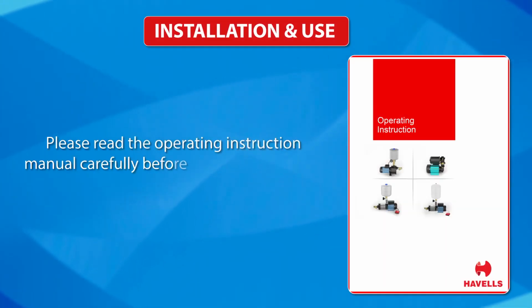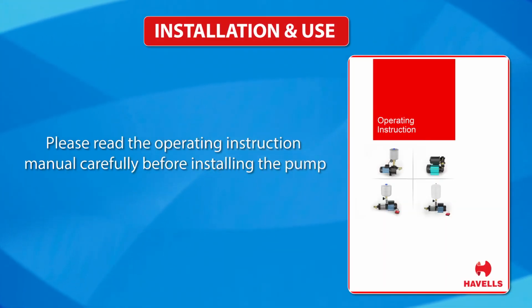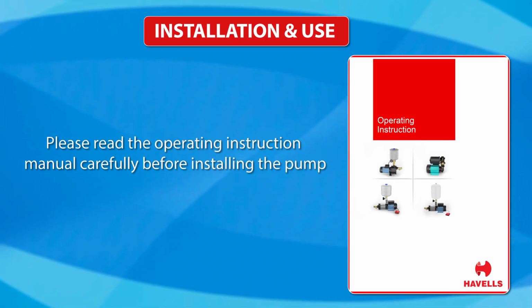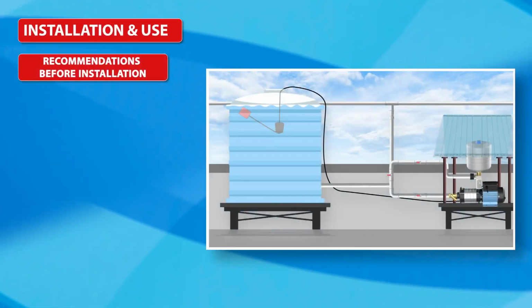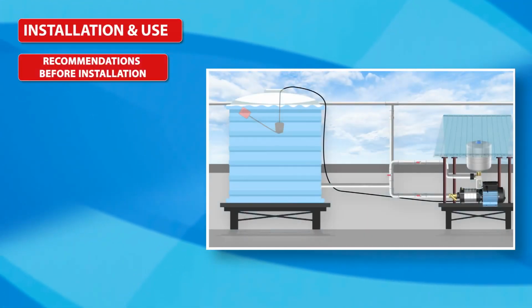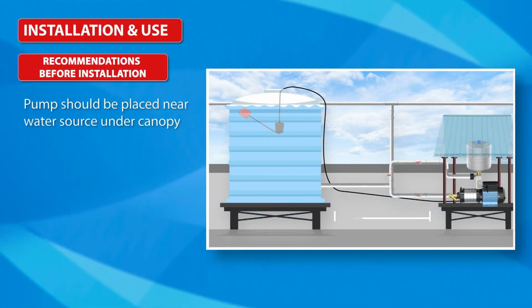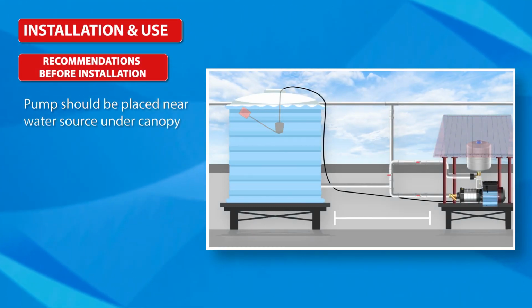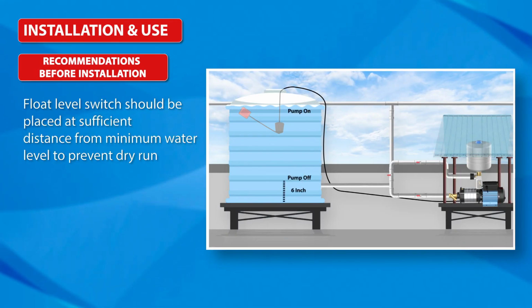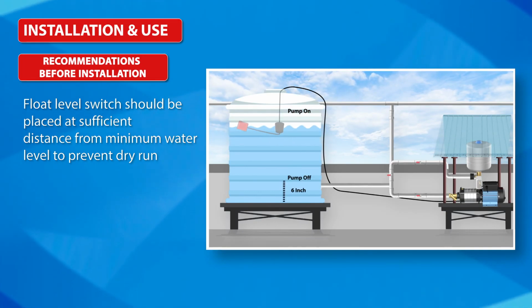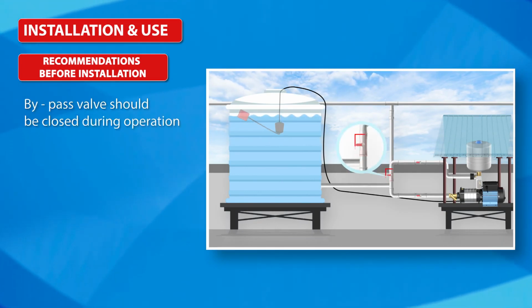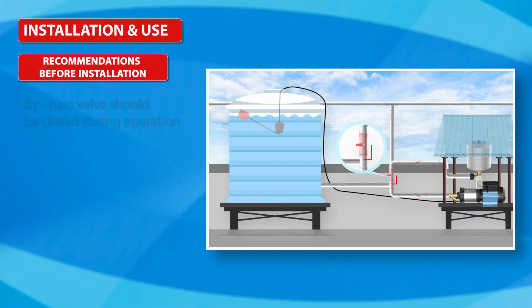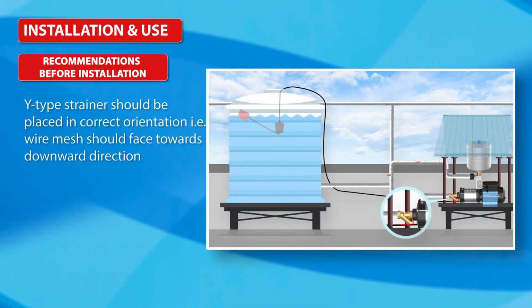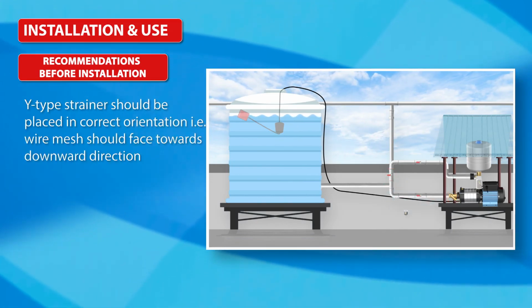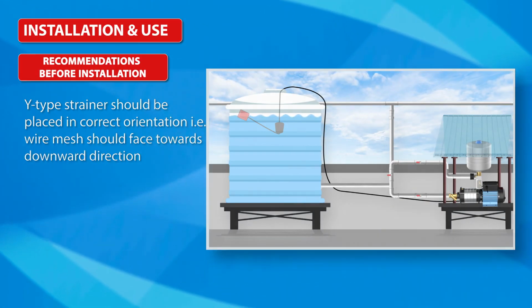Installation and use. Please read the operating instruction manual carefully before installing the pump. Some recommendations before installation: the pump should be placed near the water source under a canopy. The float level switch should be placed at a sufficient distance from the minimum water level to prevent dry run. The bypass valve should be closed during operation and the Y-type strainer should be placed in the correct orientation, that is, the wire mesh should face downward.